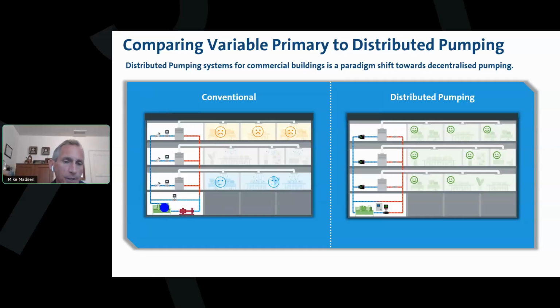Here's my primary pump, my chiller, my bypass with the motorized control valve, 3 air handler units, and 3 motorized control valves. So often when you guys go in to evaluate these buildings, they say, hey, we want you to propose some energy saving options for our building. The current system's out of balance. I've got some zones that are too hot, some that are too cold. What can you recommend for us where we can save energy and get better comfort in the space? And that's where you recommend distributed pumping.